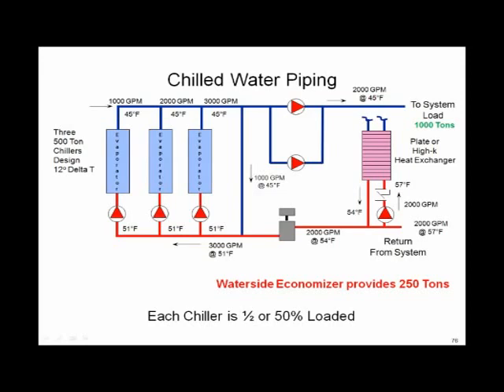I'm going to get 250 tons of free cooling by running that 57-degree water through one side of my plate heat exchanger, the other side of the plate through a cooling tower. I get free cooling, and I'm knocking down the return temperature to 54 degrees. So my chillers are not going to work as hard. I'm going back to the chiller plant now at 54 degrees versus 57. Do you see that? And when I do that, I take the load down significantly. And as you can see, as the waterside economizer works harder and harder, that return temperature goes down.